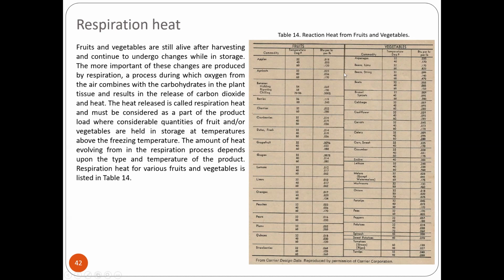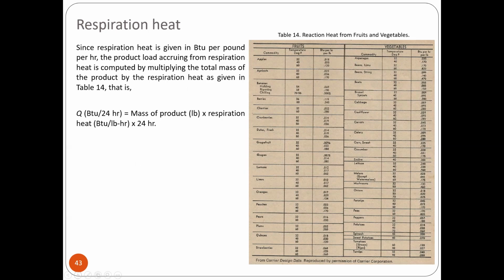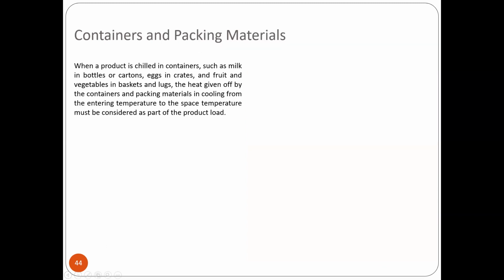So yan, fruits, vegetable, ito mga value niya, BTU per hour, temperature. Ito yung ano. Since respiration heat is given in BTU per pound per hour, the product load accruing from respiration heat is computed by multiplying the total mass of the product by the respiration heat as given in table 14. Q in BTU per 24 hours is mass of product in pounds times respiration heat, BTU per pound per hour, times 24. Okay? Ayan.